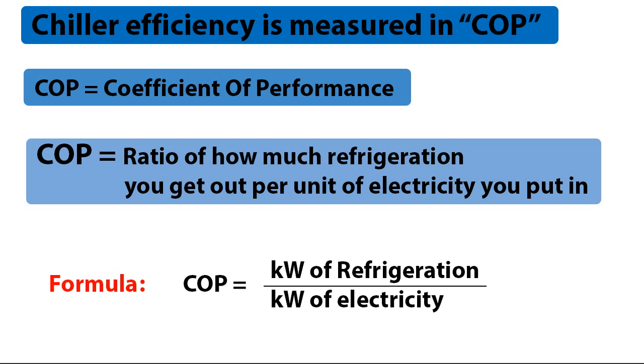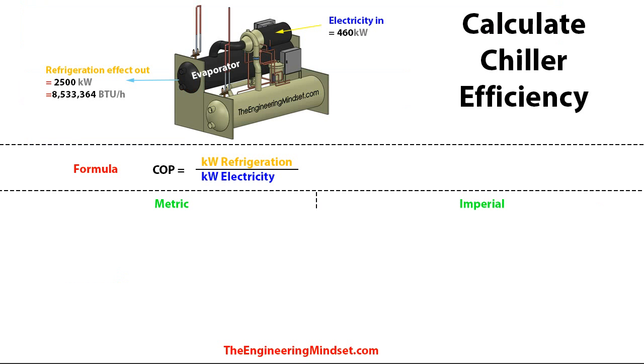Now the formula for this one is very simple. The COP is just the division of the kilowatts of refrigeration divided by the kilowatts of electricity. So we're going to do the calculations on this and we're going to have a look at both the metric and imperial formulas and calculations for that.